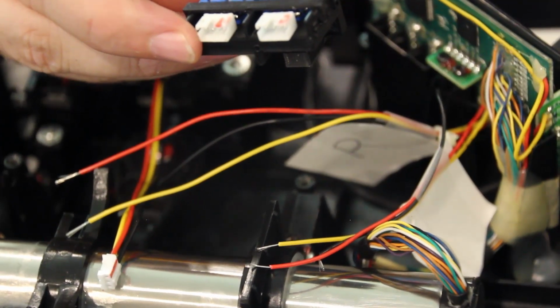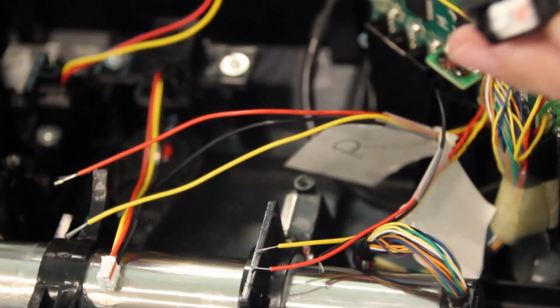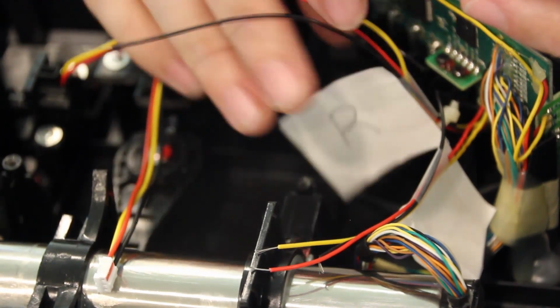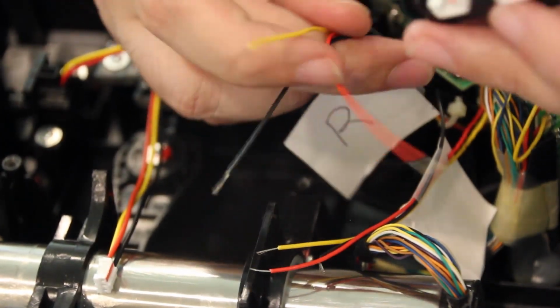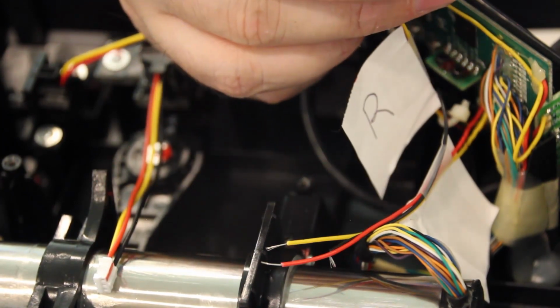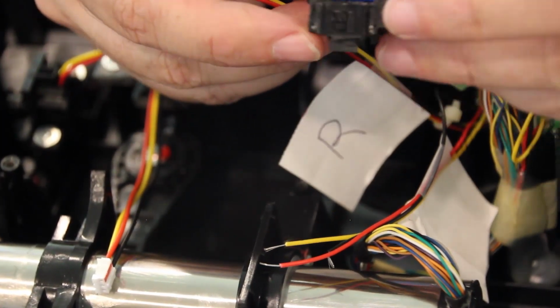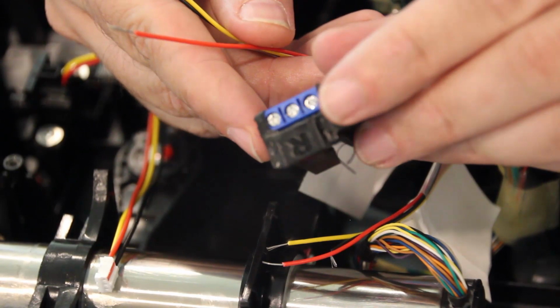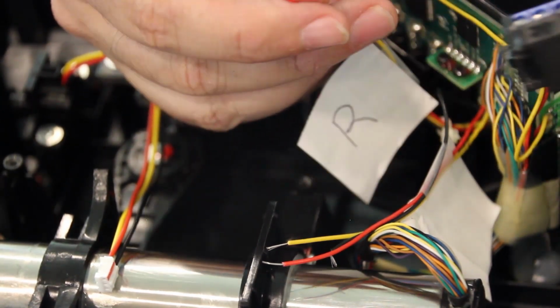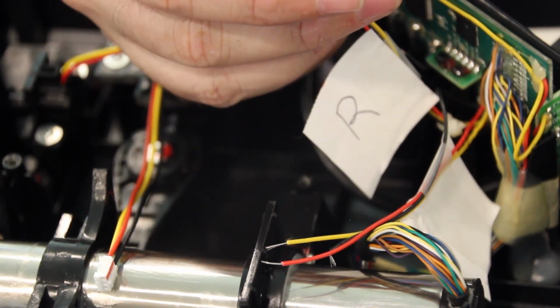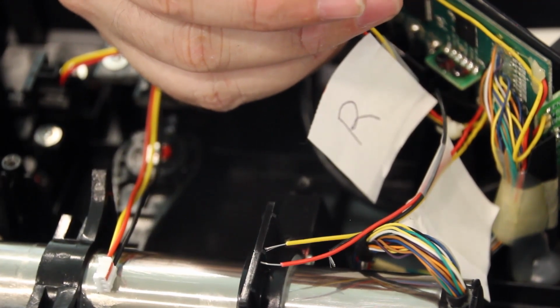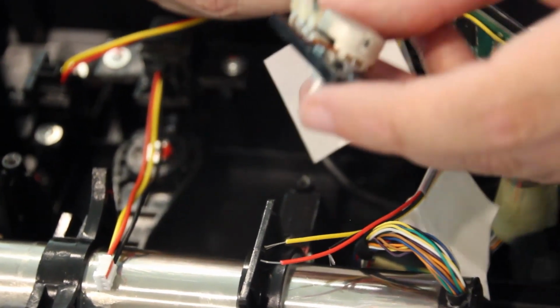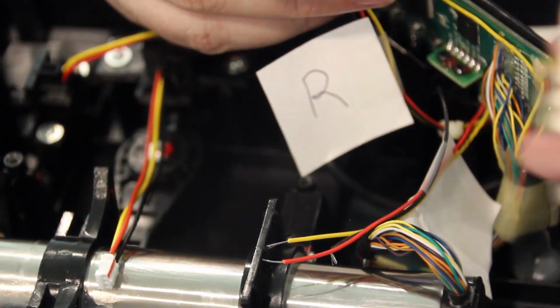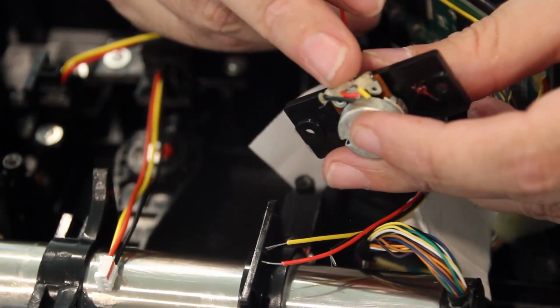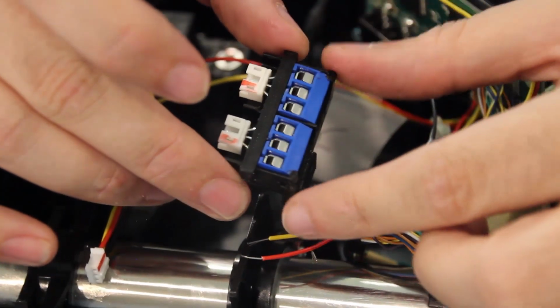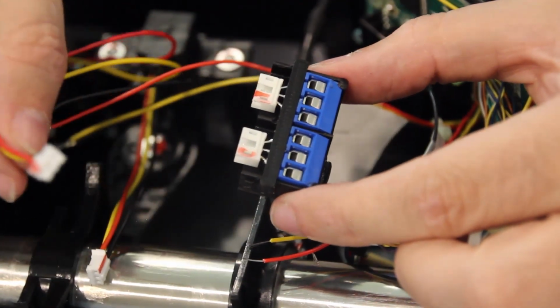We have to follow how they came out of these potentiometers, almost as if we're crossing the wires here. So we'll take our pre-labeled roll wires that we just stripped, look for the roll side on the bus bar, see the R there, and assemble it just like it was originally: yellow, red, black. The only two cables that are actually going to be the same between the Hall effect cabling and the original are our black cable.